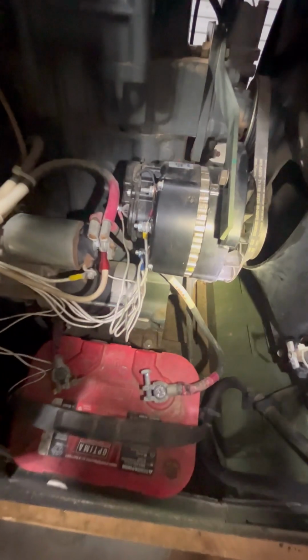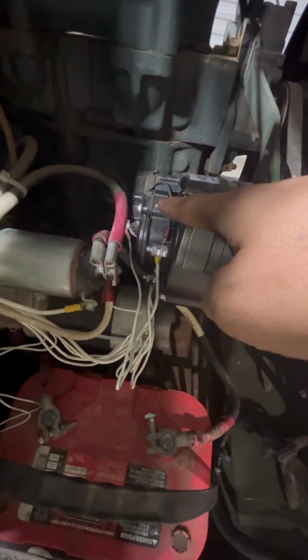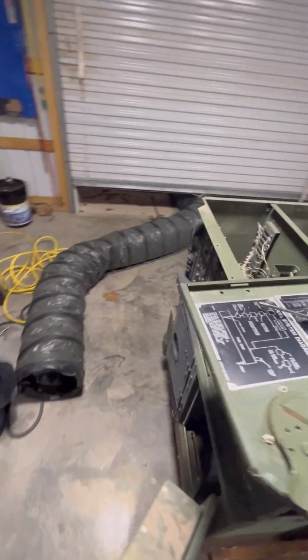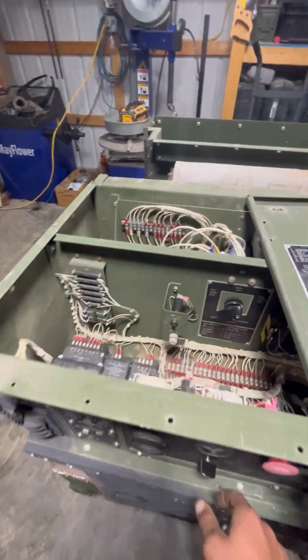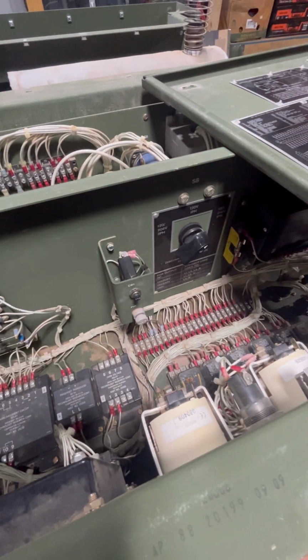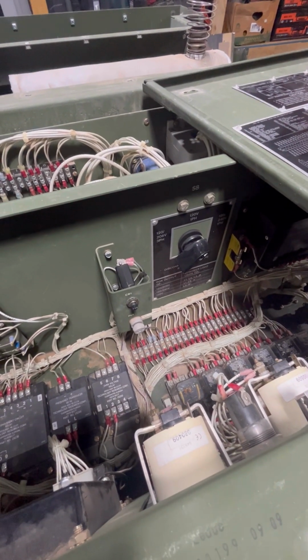Okay, so I switched that wire from that terminal down to the exciter. And usually the CB1 breaker trips within seconds of the machine being running, of the generator being running. So let's see if it trips.